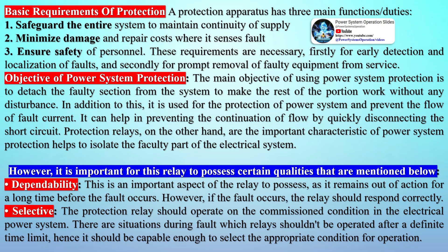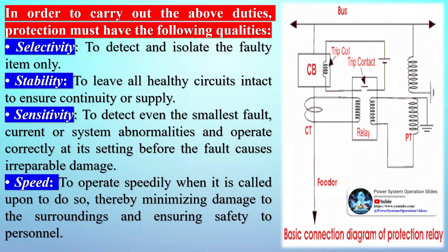In order to carry out the above duties, protection must have the following qualities. Selectivity: to detect and isolate the faulty item only. Stability: to leave all healthy circuits intact to ensure continuity of supply. Sensitivity: to detect even the smallest fault current or system abnormality and operate correctly at its setting before the fault causes irreparable damage. Speed: to operate speedily when called upon, thereby minimizing damage and ensuring safety to personnel. To meet all of the above requirements, protection must be reliable, which means it must be dependable — it must trip when called upon to do so — and secure — it must not trip when it is not supposed to.